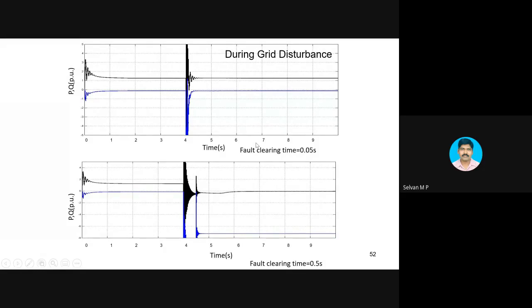But suppose the fault clearing time is 0.5 seconds, because 0.05 seconds is very, very ambitious, right? Sometimes the sensing time of the relay and the circuit breaker operating time may be slightly higher, and it may not be able to provide the proper trip signal within this time. 0.05 seconds means within 3 cycles it has to work. Of course, fast acting circuit breakers are available and the relays are able to sense, but that highly efficient protection system is used only in transmission lines, not in the distribution systems, where the relays will have certain time to sense and the circuit breaker has to operate. So definitely it takes a little more time. Even if it operates at 10 cycles, it takes 0.2 seconds. So here I have considered the worst case, 0.5 second.